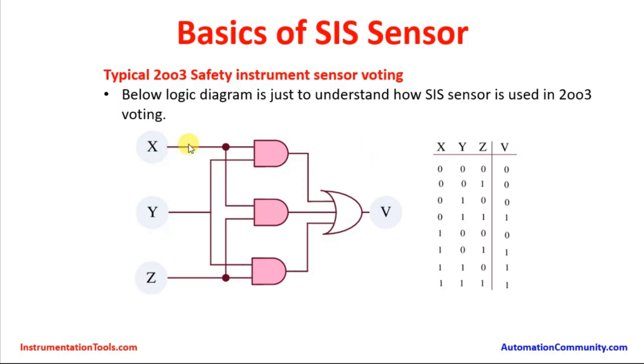In the case of two-out-of-three voting, sensors X, Y, and Z are three different sensors and V is the output. Whenever two sensors — for example Y and Z — go high, the output will be one. This is a simple logic truth table showing how safety is handled and the equipment is protected suitably in a safe way according to the process requirement.